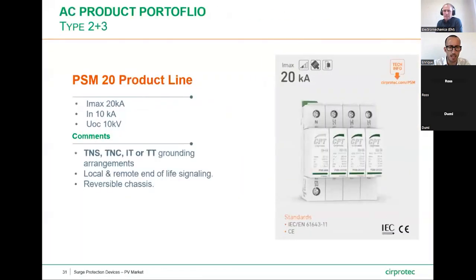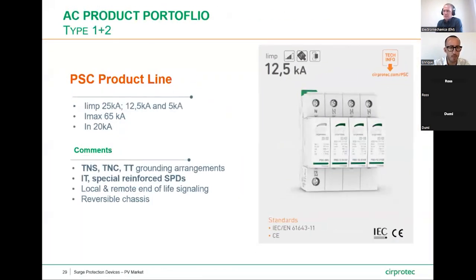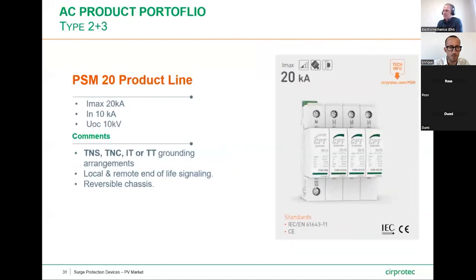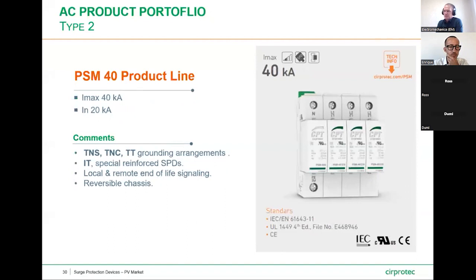Why does the PSM20 have 320 volt max L to N UC and the PSM40 has a 270 volt max line to neutral UC? The inverter supply asks for 265 line to neutral protection. Well, can you repeat the question, please? Okay, I'll try and go slow. I will go to the slides also of the products you are saying. The PSM20 has a 320 volt max line to neutral UC rating, and the PSM40 has a 270 volt max line to neutral UC rating. So the customer is asking that the inverter supplier asks for 265 volts line to neutral protection.